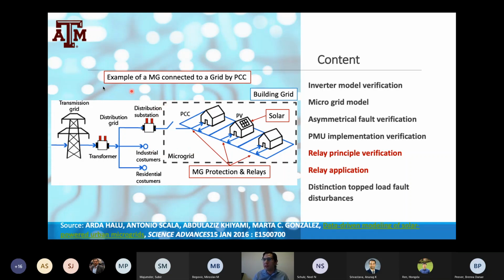This is a microgrid that is connected to a traditional transmission line through the point of common coupling. Our focus now is on an autonomous mode type of grid, which basically consists of PV solar panels. They can be rooftop or not rooftop, like on the floor. The portion I want to address is the building stage: how we reach a very realistic scenario for building the inverters, the model itself, and the microgrid model, so we can test the protections and the development of the relays with higher accuracy.